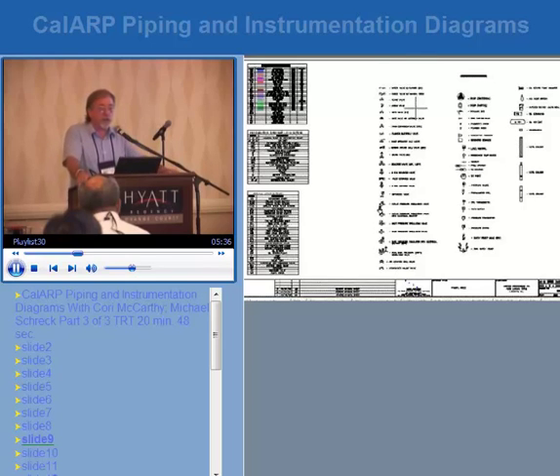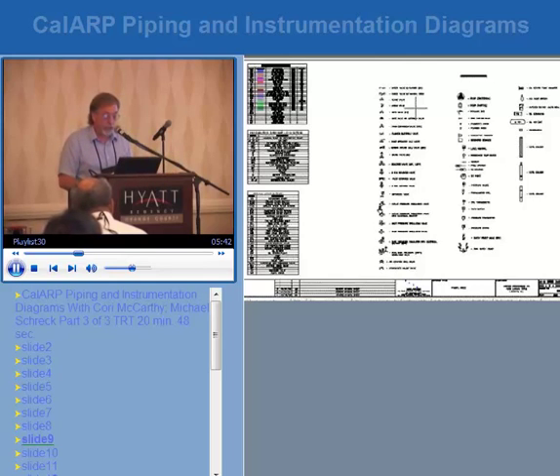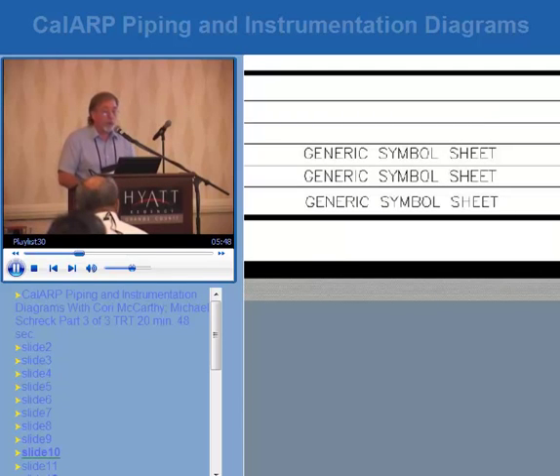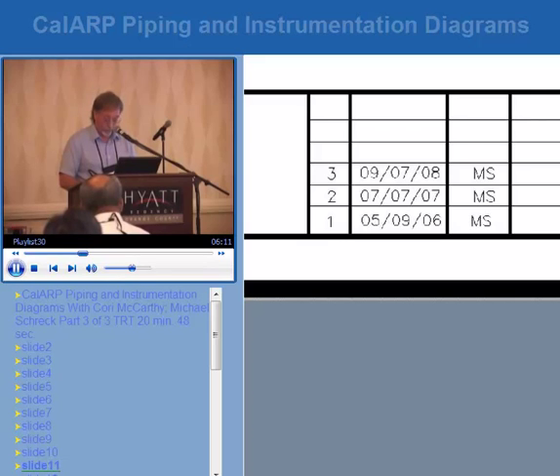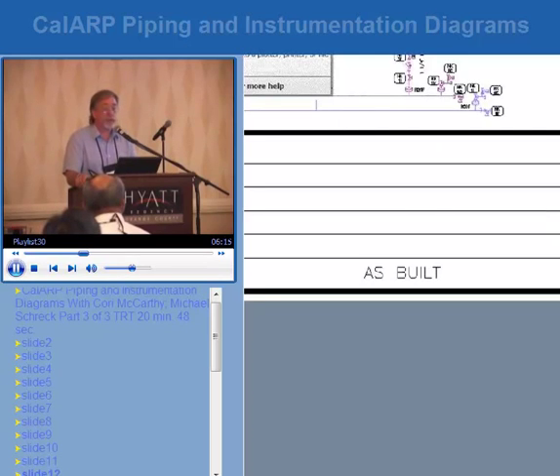On the first sheet of the drawing set, you're going to have your legend and symbol sheet. Somewhere on that main drawing you'll have a revision number or date of when it was last updated — revision number one, two, three, and so on. On the P&IDs themselves, look for the two words: 'as built.' It's not required that they put that on there, but look for the right revision date and match it up to their last management of change or construction.